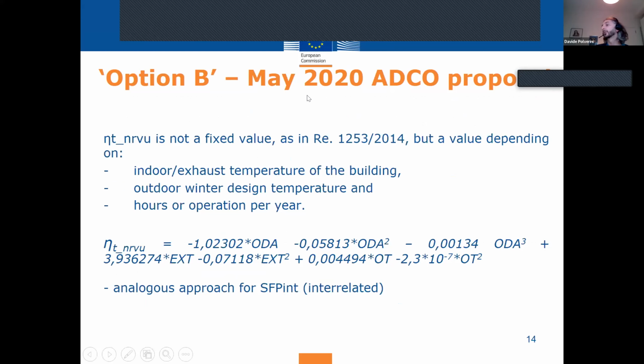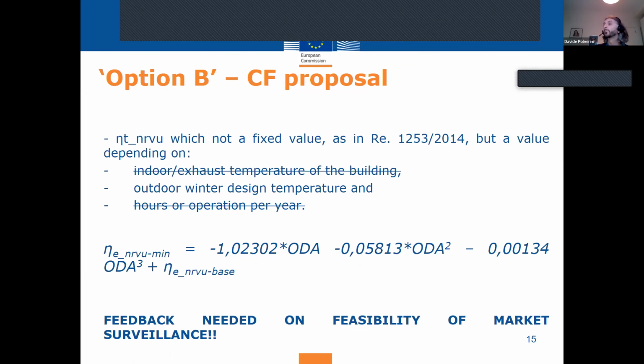We had the first meeting in 2020 with market surveillance authorities, where we proposed the first version of this model, of this relationship. For the meeting of last February 2021, with a consultation forum, the important one where we officially discussed the draft measures with, again, member states and industry, we presented a simplified version of the heat recovery efficiency dependent on the geographical installation, basically blocking parameters such as the indoor and exhaust temperature of the building, the hours of operation per year, and leaving as only variable the outdoor winter design temperature, which again can be linked to the geographical location.